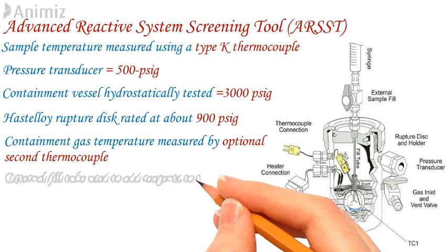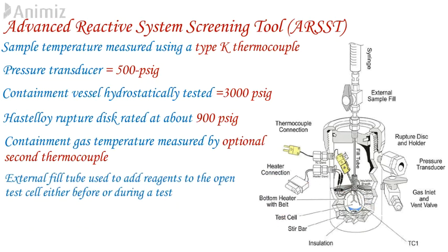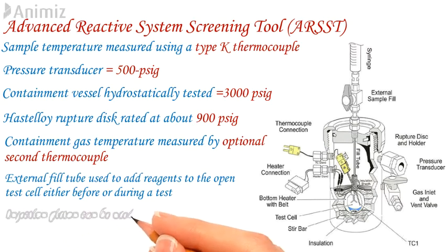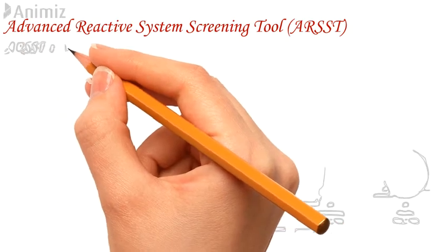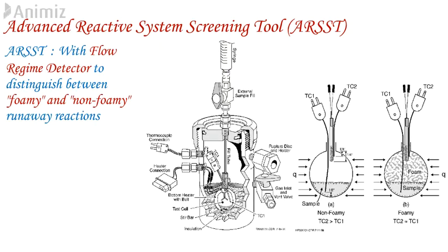An external fill tube can be used to add a reagent to an open test cell either before or during the test, and an injection piston can be used to add a reagent against elevated back pressure. ARSST can also be available with a flow regime detector, which allows the operator to distinguish between foamy and non-foamy runaway reactions. It comprises a small immersion heater and an attached thermocouple positioned in the upper freeboard space of the test cell, with an auxiliary control box containing a dedicated power supply for the sensors.